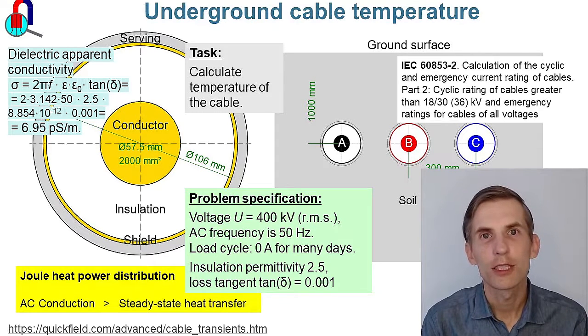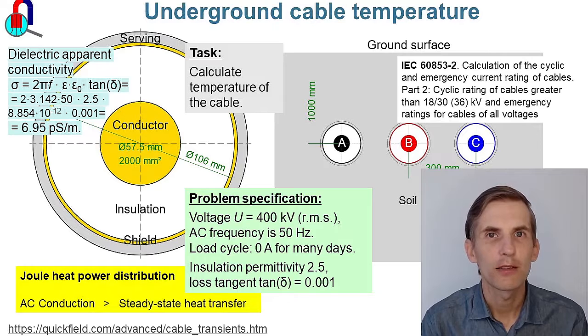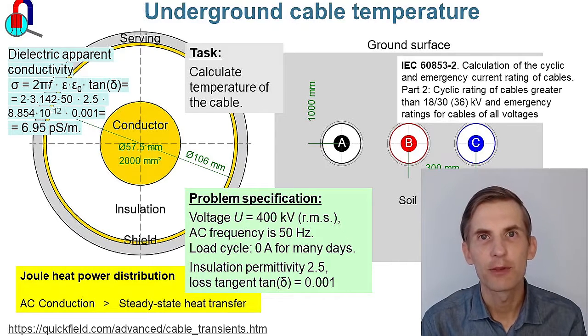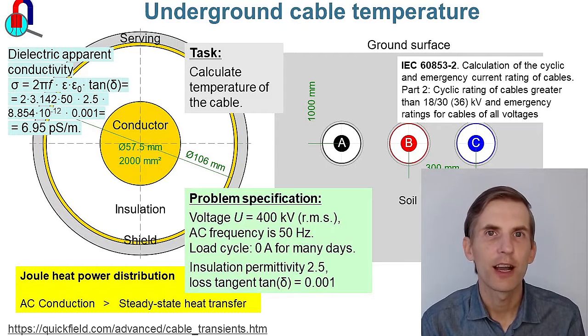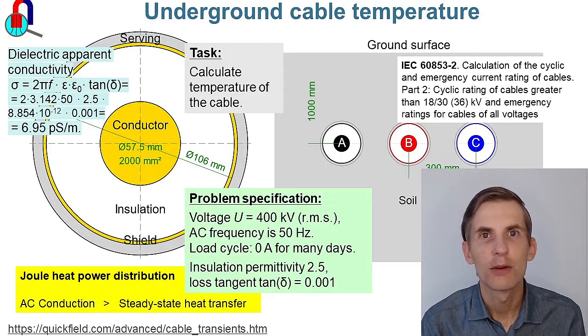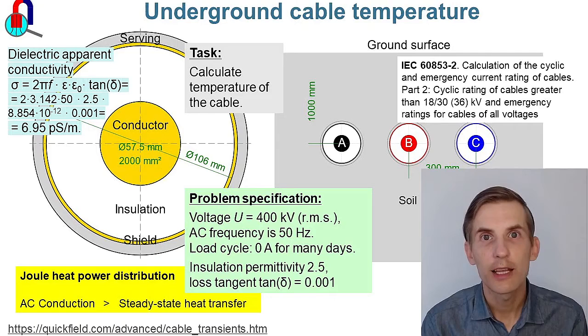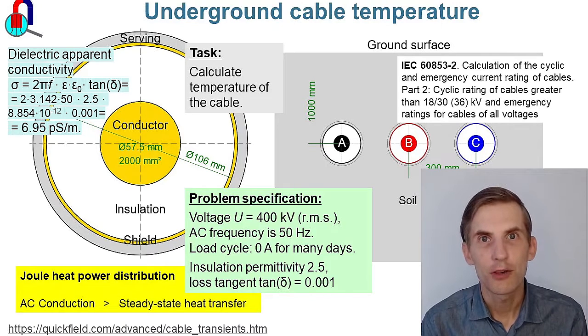High voltage underground cable temperature. We have a high voltage cable. In fact, there are three cables in flat formation. The cables are energized, they are connected to the three-phase AC voltage source, but the load is not connected. Our task is to calculate the temperature of the cable.